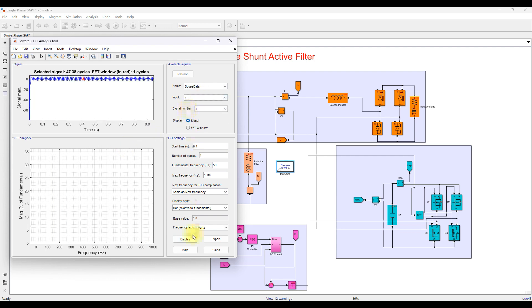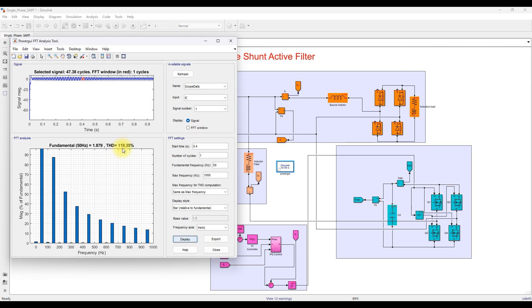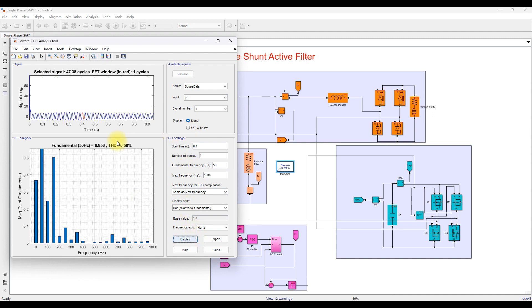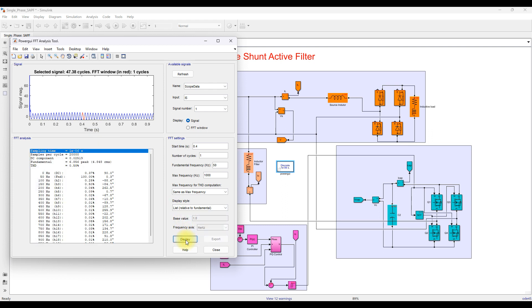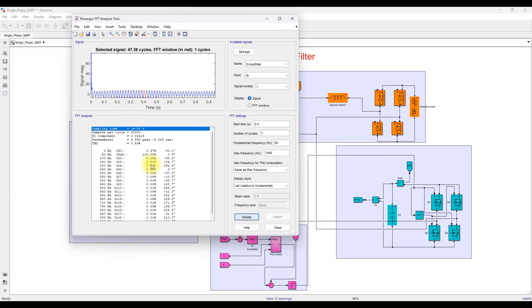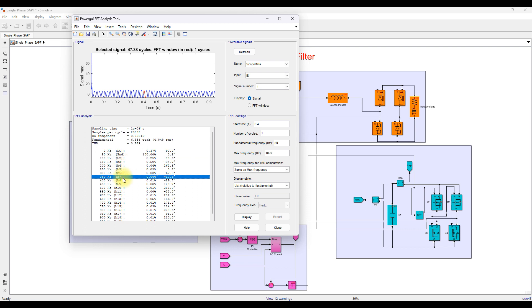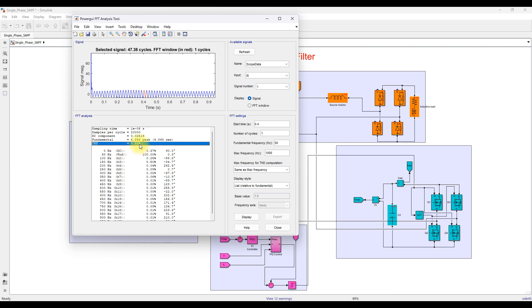The THD of the compensation current is 119.35%, meaning it injects the required compensating current, and after injecting that current, the source current automatically changes to sinusoidal. The source current THD is around 0.58%. Looking at individual harmonic orders, H3 is 0.5%, H5 is 0.09%, H7 is 0.06%, so all harmonics are under 0.5% level. The peak amplitude of the source current is 6.88 amps.